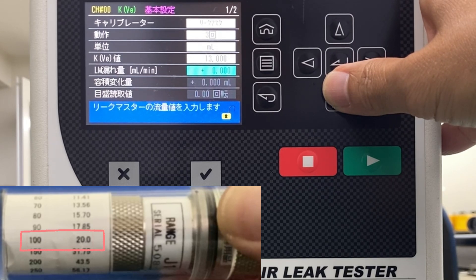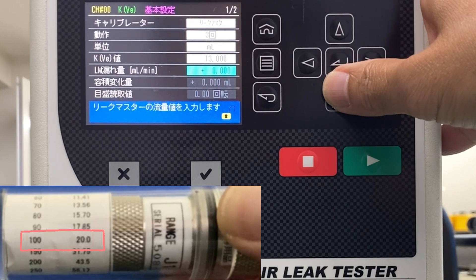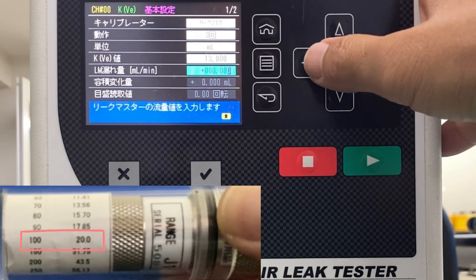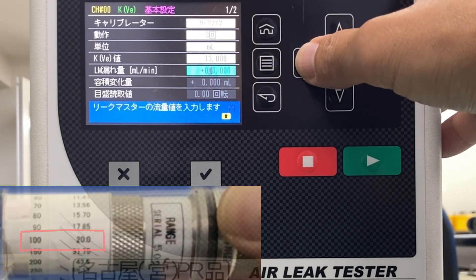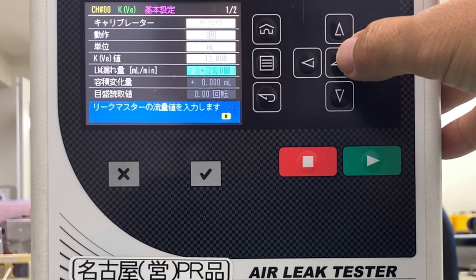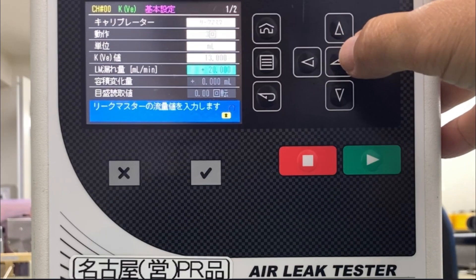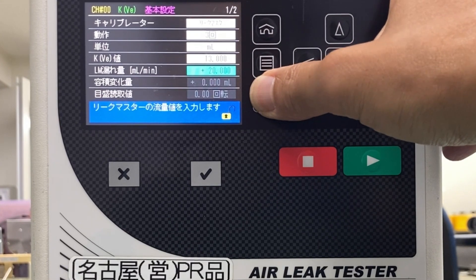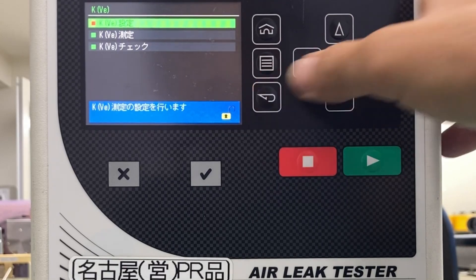Enter the LM flow rate. Move the cursor to the entry field of LM flow rate and enter the flow value of the leak master. This time we will use a leak master that leaks 20 mL per minute at 100 kPa, so enter 20. Select with the Enter key and use the cursor keys to enter the value. After entering, press the Back key twice.